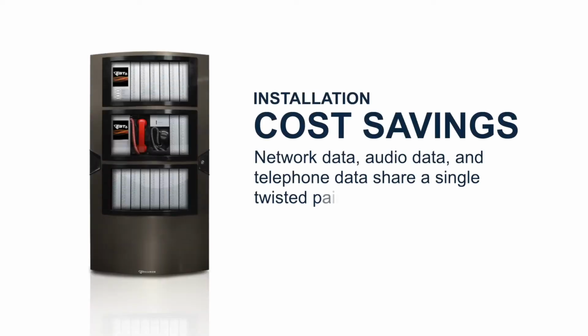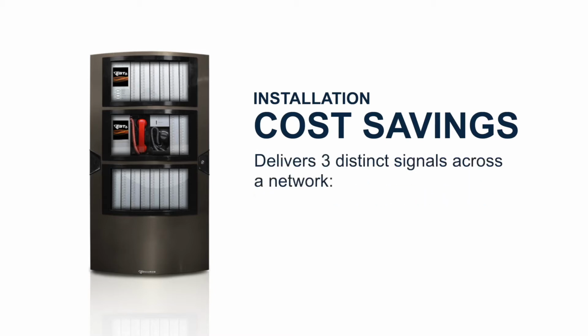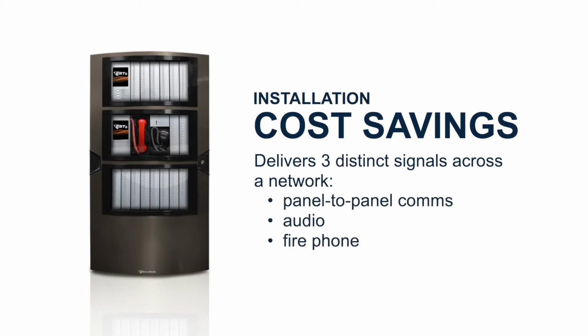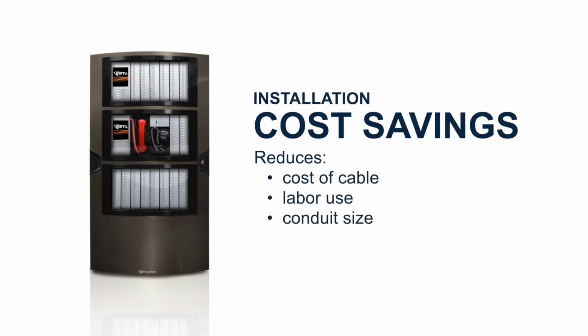So another benefit is the installation cost savings that comes along with EST4. EST4 helps you be more competitive when it comes to bids, for example, by having the capability to deliver 3 distinct signals across the network, which is panel-to-panel communication, audio, and fire phone. And all of this is done over a single pair of wires or a single fiber strand. This reduces the cost of cable, labor used to pull the cable in many cases. It also reduces the conduit size when conduit size is required to be installed between panels.